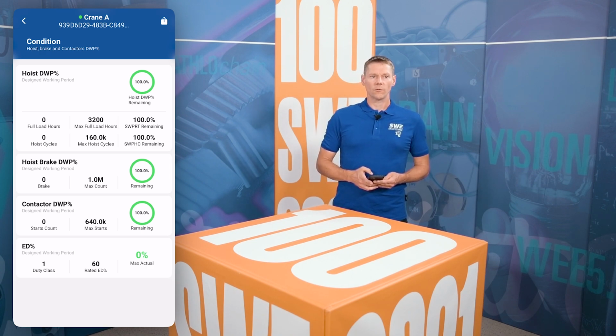Another piece of information is about the DWP of the hoist brake and also of the contactors. We see how many actions have happened during the lifetime and also the ED classification.